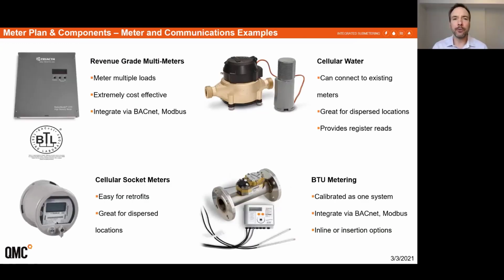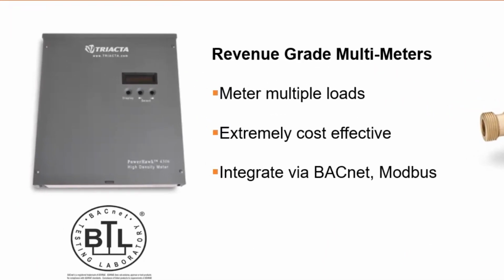So I wanted to talk a bit about meter hardware. We could do an entire presentation on each different utility type's metering equipment, but we wanted to just give a high-level review here of some of the technologies you're seeing in the market. Starting in the top left, this is an electrical meter that is referred to as a multi-point meter. What this box allows you to do is meter multiple electrical loads out of one single device. This meter in particular will do 8 three-phase 4-wire loads, whether that's at 347/600 or 120/208. What it allows you to do is very cost-effectively meter several tenants or critical loads within the building out of one device. It reduces your material costs and your labor costs.